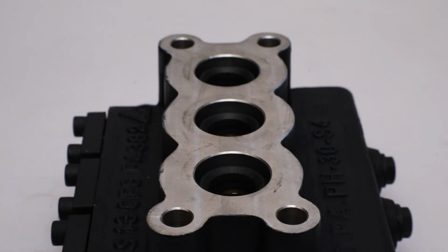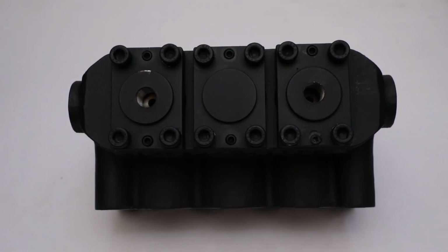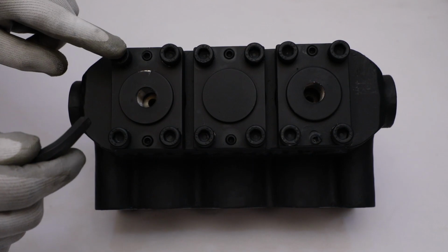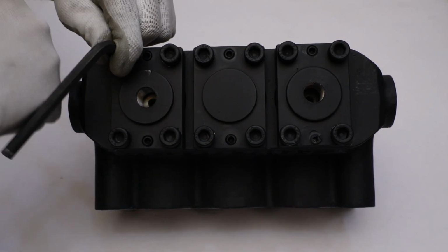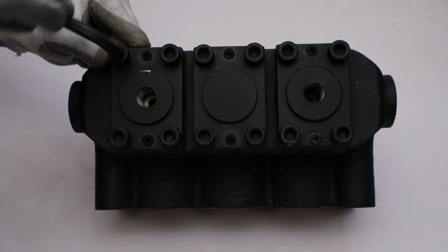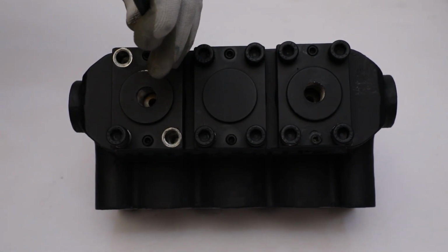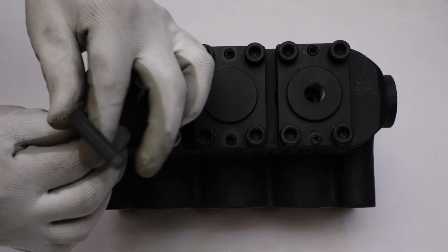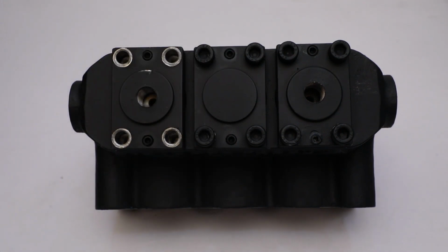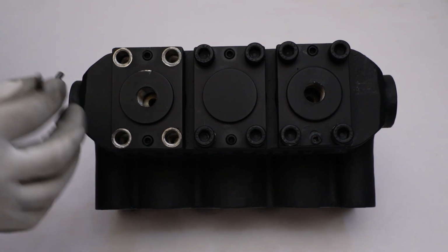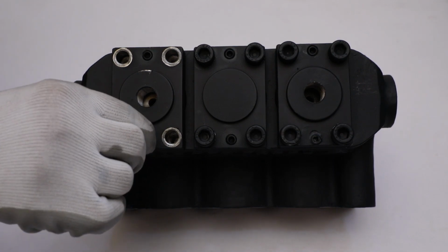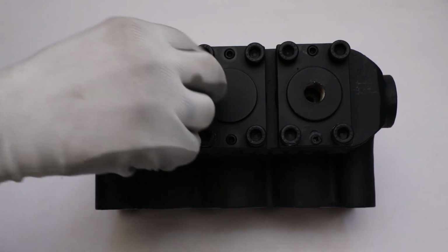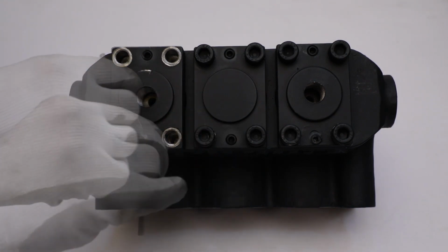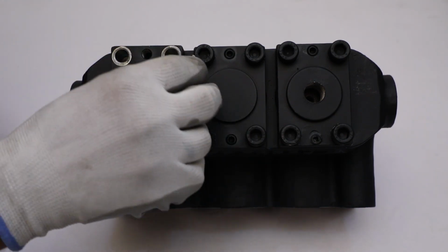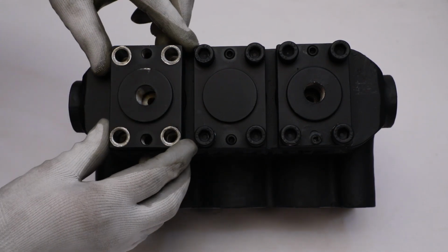Disassembly of valve assembly. Take all three packing supports and rotate the pump head from the valve holder side. Take Allen key and unscrew 4 M10 by 30 cap screws of a threaded valve holder in a diagonal manner. After that, tight grub screws one by one of same threaded valve holder, which will pull out the valve holder from the pump head. Take the valve holder.